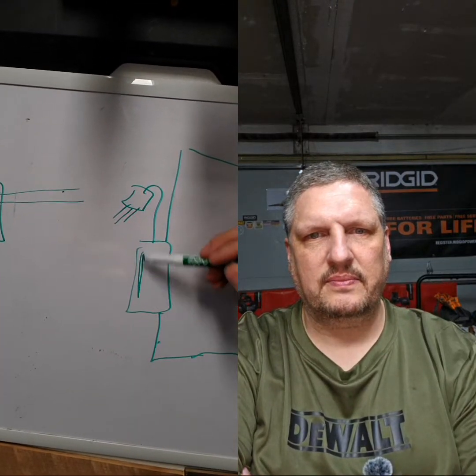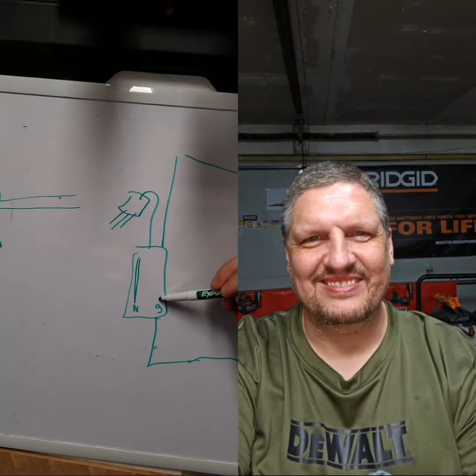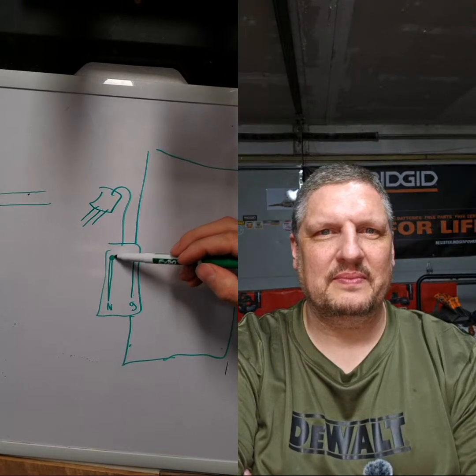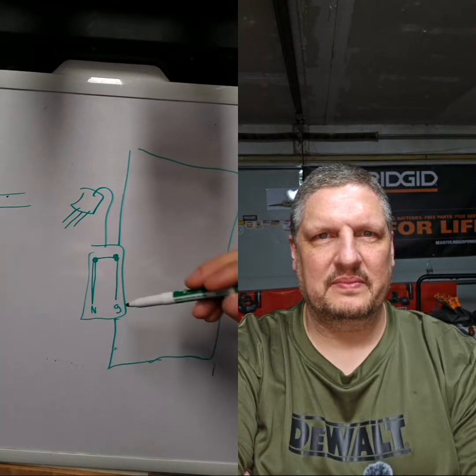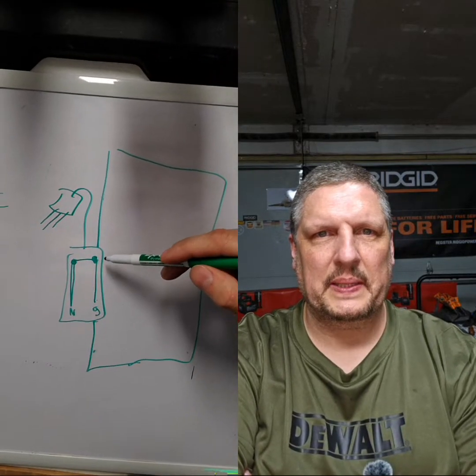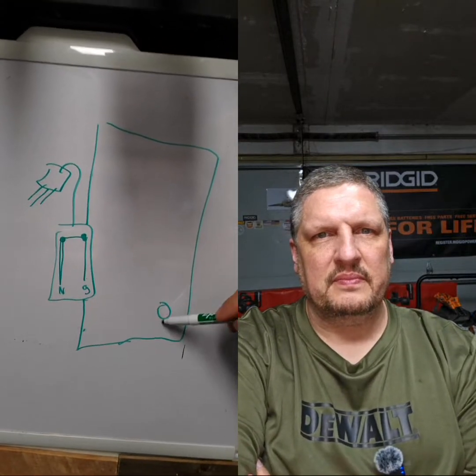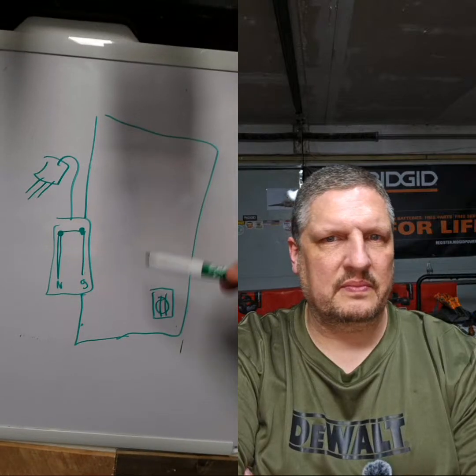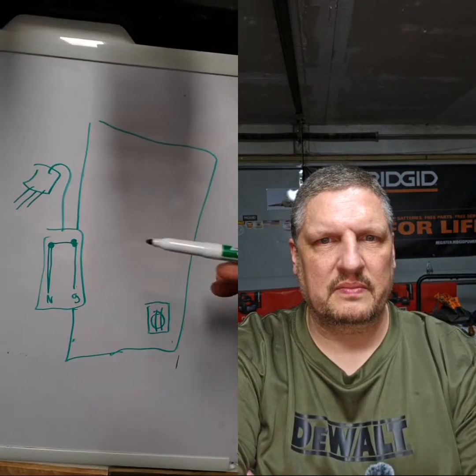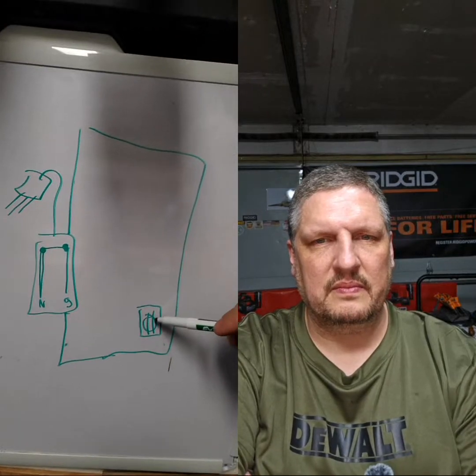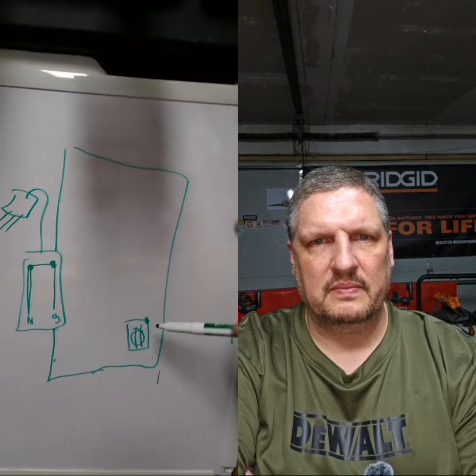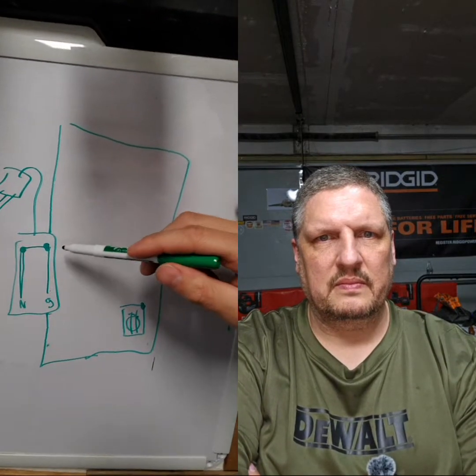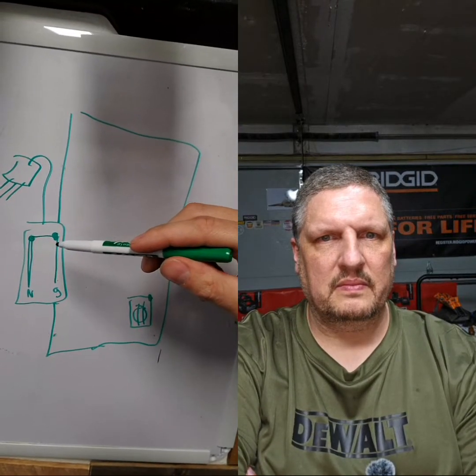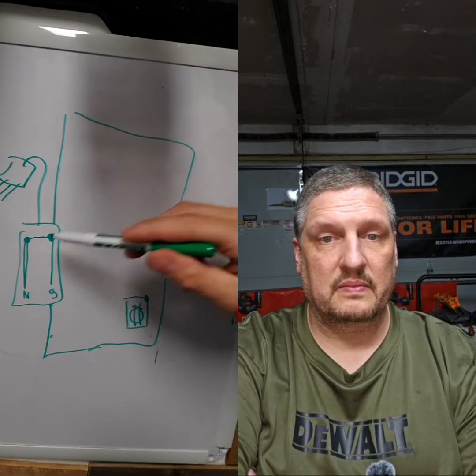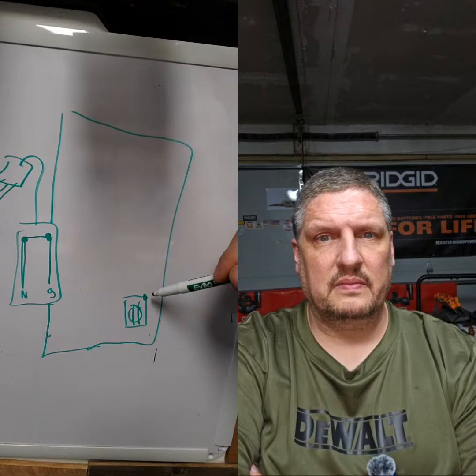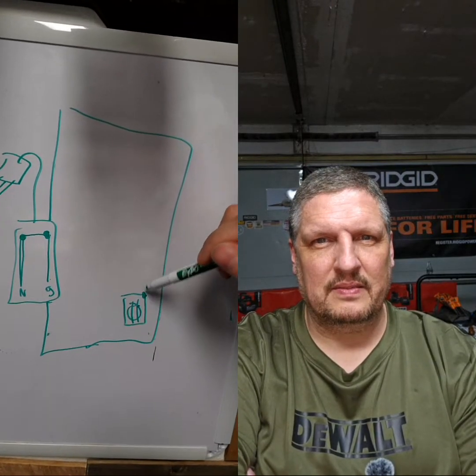Inside your panel, you have your neutral, and you have your ground here. We bond our grounds and neutrals together at the source. I'm not going to draw the hots for simplicity here. Neutrals and grounds are bonded at the source. We have a receptacle somewhere in the house. We'll just do a metal box to make it simple. It could be the case of an oven. It could be anything. It could be a rat chewed a wire, whatever happened. If your hot makes its way to the metal box case, we have 3 wires: a hot, a neutral, and a ground that went to this panel to feed this plug. We had a 20 amp breaker, 3 wires, hot, neutral, ground over here. I'm just going to draw the ground for simplicity.